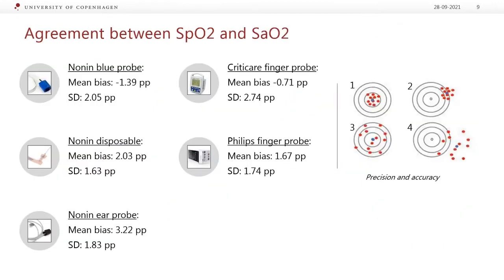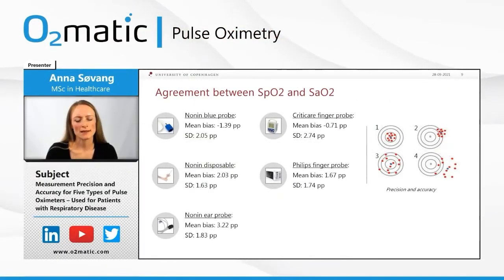And here are the results from the comparative analysis between SpO2 and SaO2. As you can see, the Nonin disposable probe, the ear probe, and the finger probe all have positive mean biases, and therefore overestimated the SaO2 value. If we look at the ear probe, it had the highest mean bias. So on average, it measured above 3 percentage points too much. On the other hand, the Nonin with the blue probe underestimated, and the Criticare underestimated a little as well. However, this was statistically insignificant.